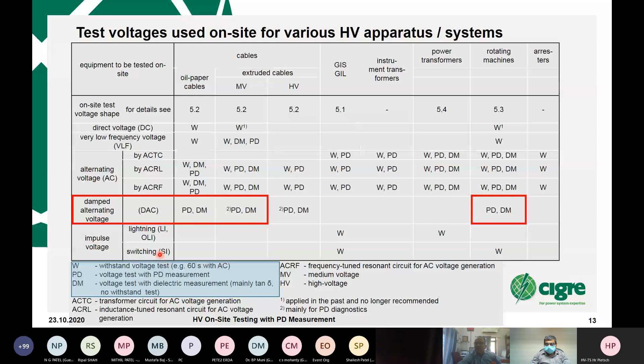As I said, how are the circuits? This is a typical normal circuit for transformer testing, compensated of course, but if it's a big cable or long cable, you need a lot of energy or power, up to 10, up to 50 MVA. So you really need a very powerful power supply and transformer, and it's not always suitable. That was the reason to invent, 30 years ago or so, the 0.1 hertz very low frequency resonant test system.